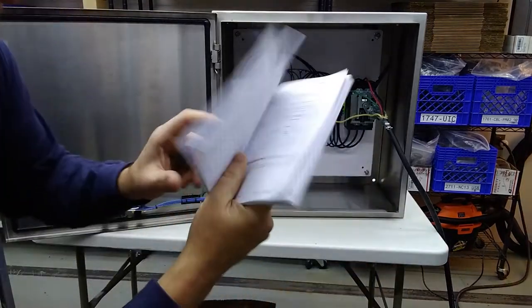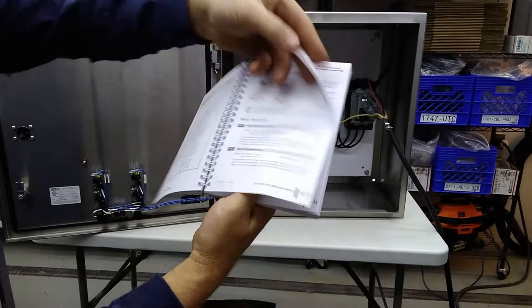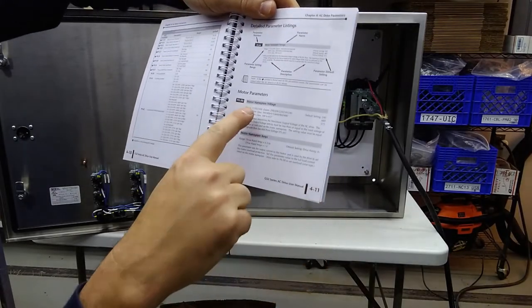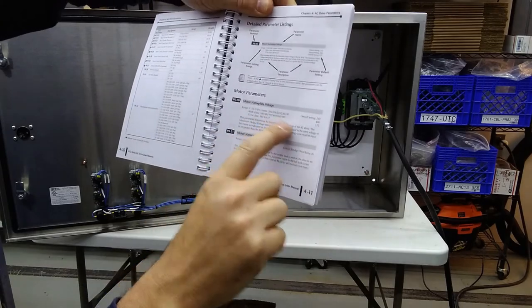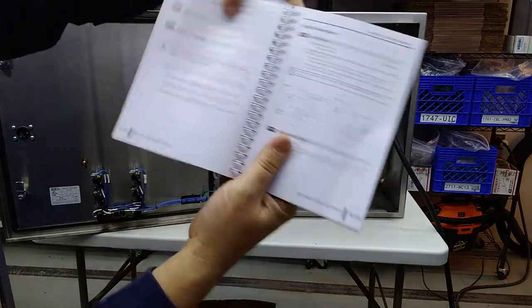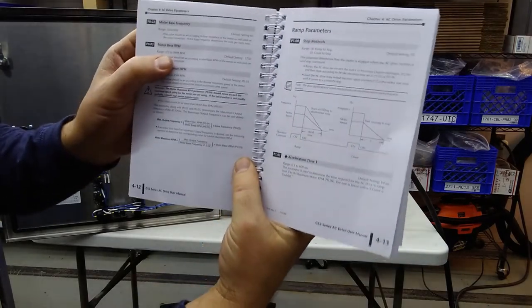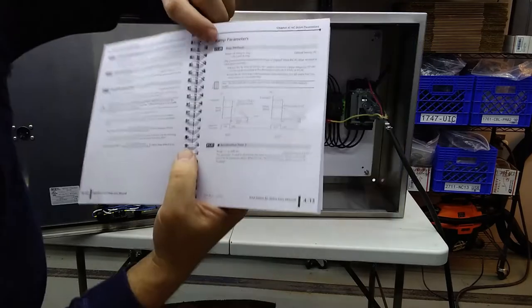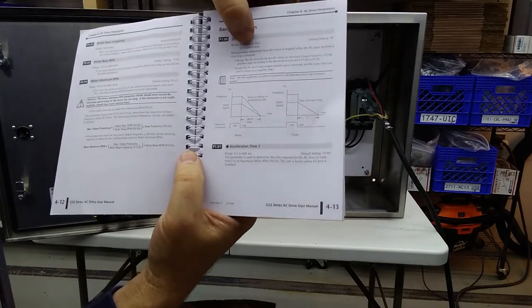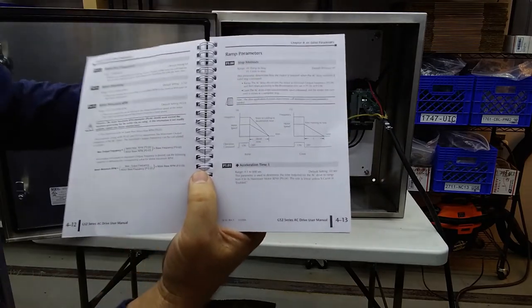There are a few settings to be concerned with, mainly starting on page 4-11 of the manual. You need to put in your nameplate voltage, but mainly your nameplate amps, base frequency which is 60 Hertz, and base motor RPM. And the stop method — it can either ramp to stop, which is what I currently have it set for, or coast to stop, which means as soon as you hit the stop button, it just coasts down.